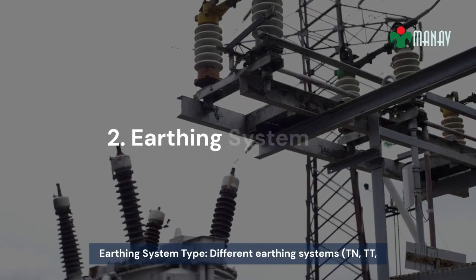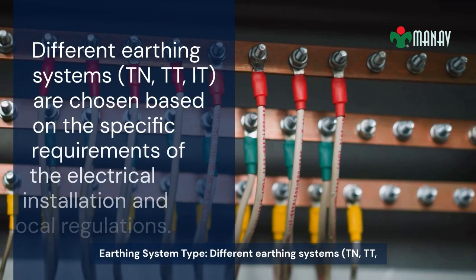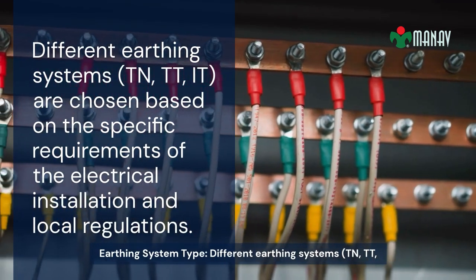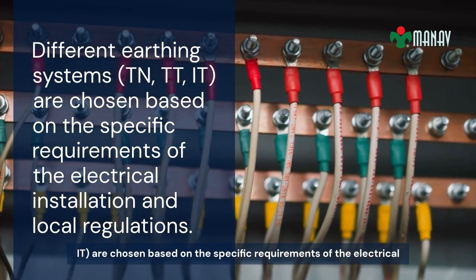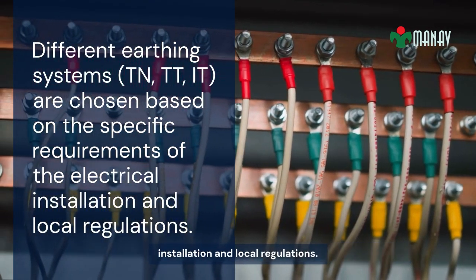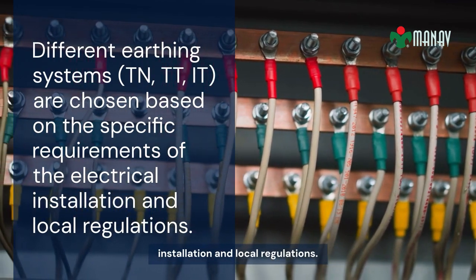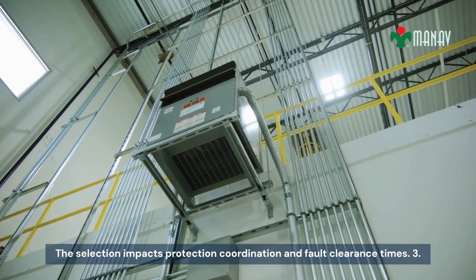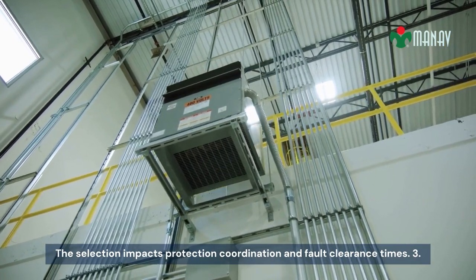2. Earthing system type. Different earthing systems, TN, TT, IT, are chosen based on the specific requirements of the electrical installation and local regulations. The selection impacts protection coordination and fault clearance times.